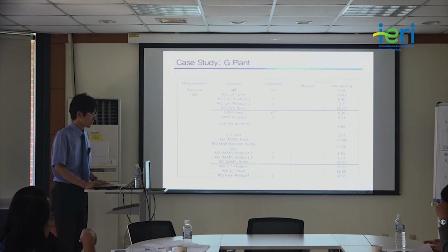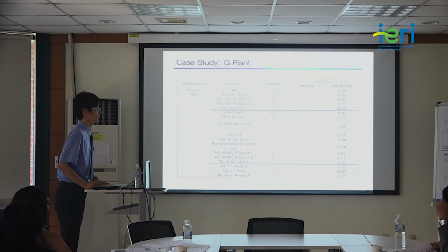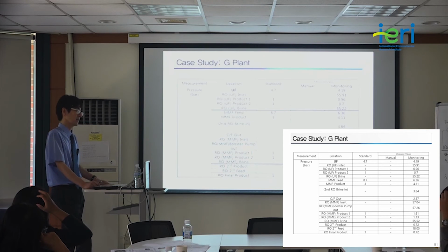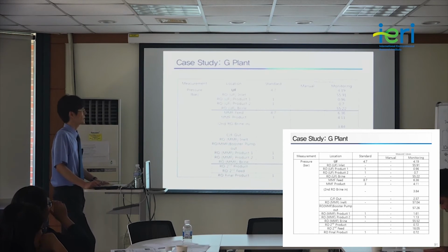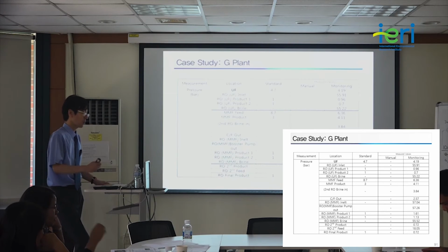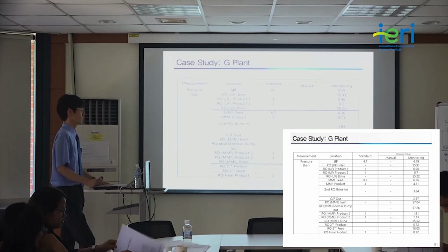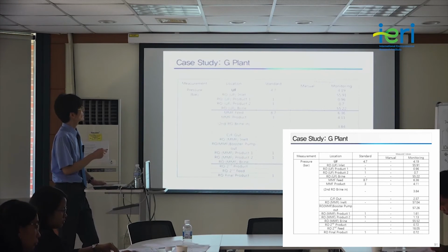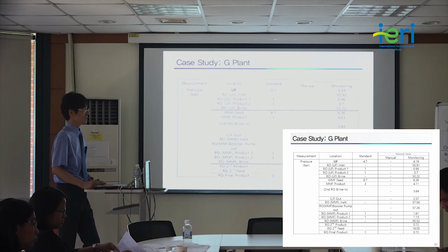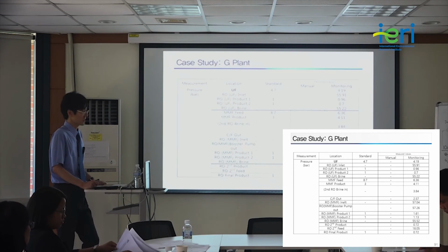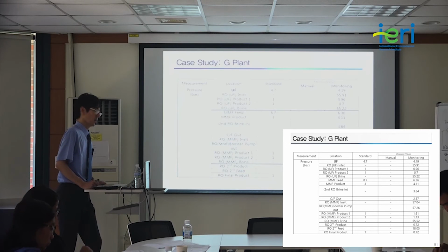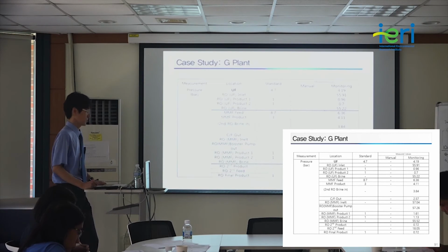And in this case, when we monitor this plant, what you can see is the pressure and the energy consumption by the whole plant and by the unit process. And this is one of the examples of the operational record. If you look at that, you see how much pressure is used, how much pressure is wasted, and how much pressure is required to operate this pre-treatment and reverse osmosis system.